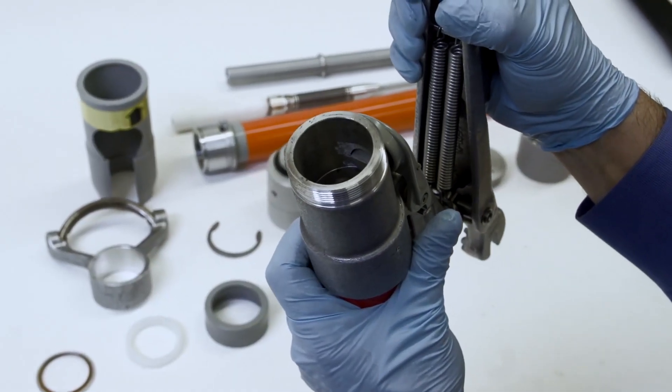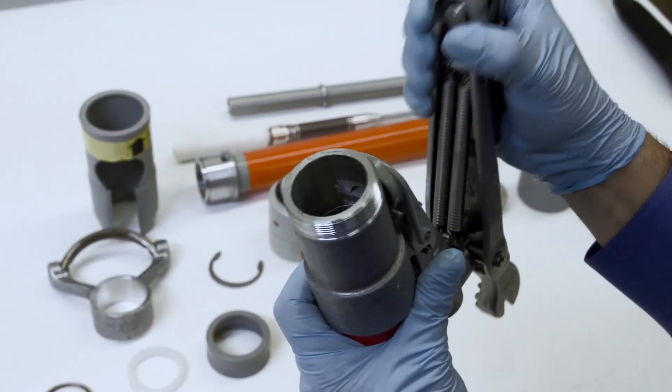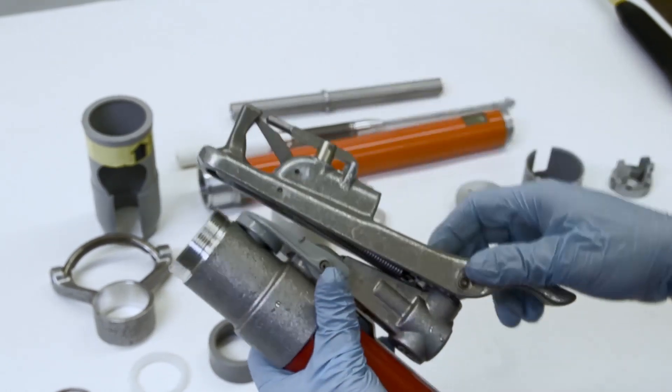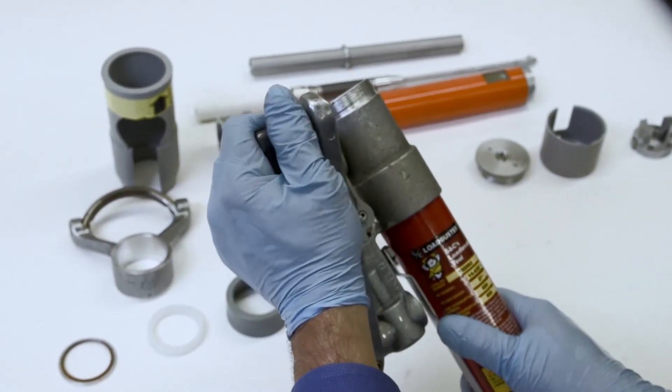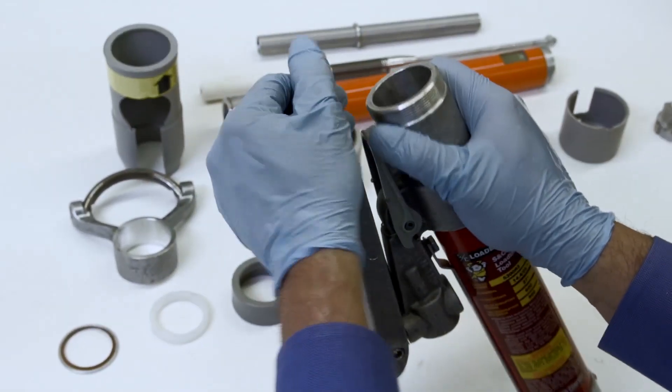Pull the hook frame assembly away from the chassis and inspect the springs. Replace them if damaged or severely corroded. The entire assembly should also rotate freely side to side.